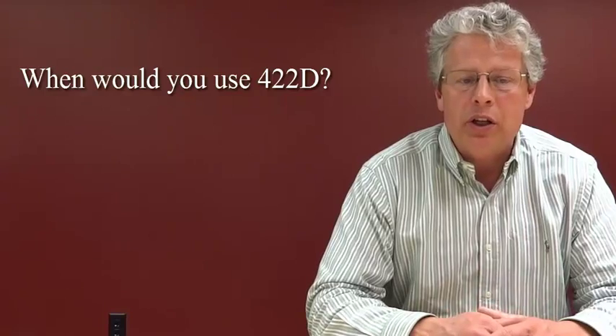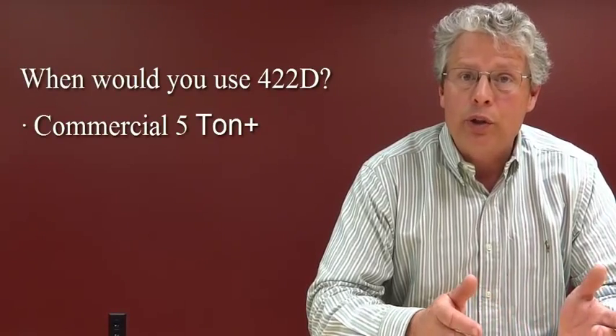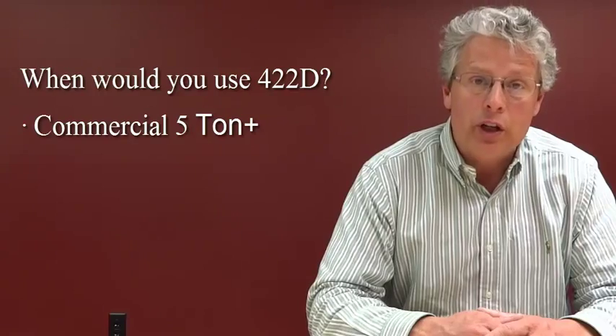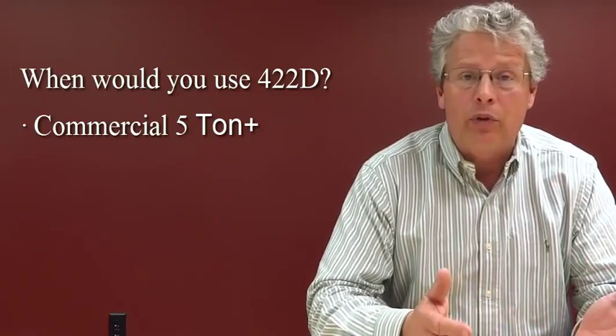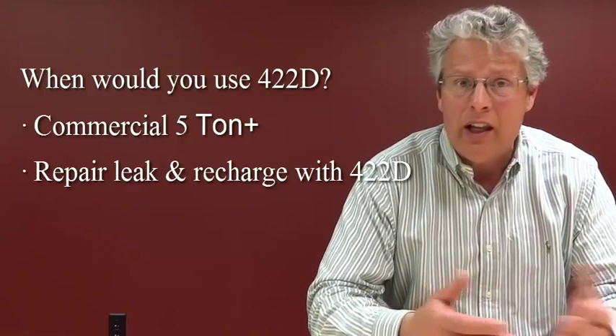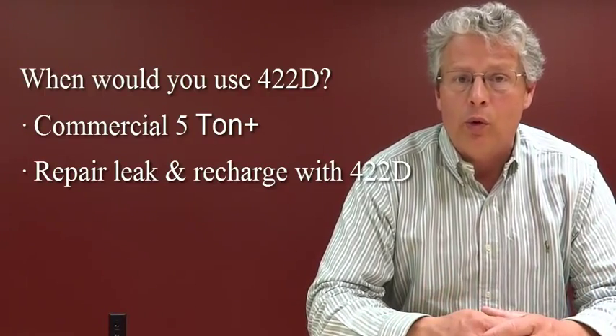Now, when would you use this? Typically, on commercial units, five tons and above. If you've got a single circuit, you would use it like in a seven and a half ton package unit. You've got a refrigerant leak. You repair that leak. You recharge the unit with 422D.